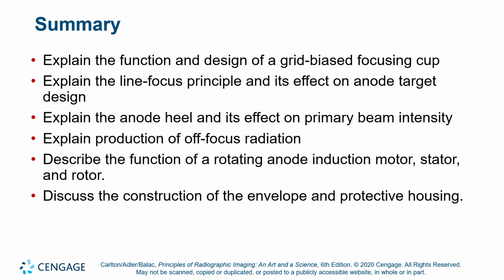It alternates polarity between positive and negative charge, such that you get a machine gun like bolus, so tiny little bursts of X-ray pulses at high frequency, and typically that frequency matches the data dump frequency of your digital detector on your fluoroscope, and so you get 30 frames per second motion picture. It's very much like video games. That's how video games do motion picture. It's actually 30, greater than 30 still frames per second, with subtle little changes in between the frames, creating the illusion of a motion picture. And so with that grid bias design and pulse fluoroscopy, we can significantly save dose with digital fluoroscopy.